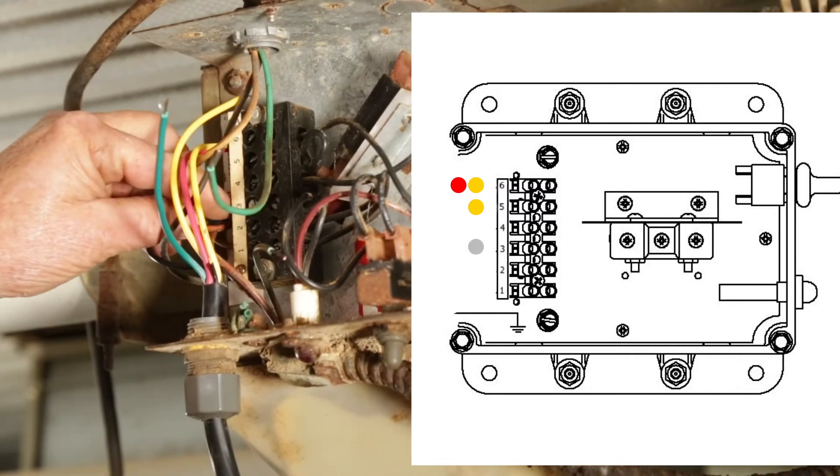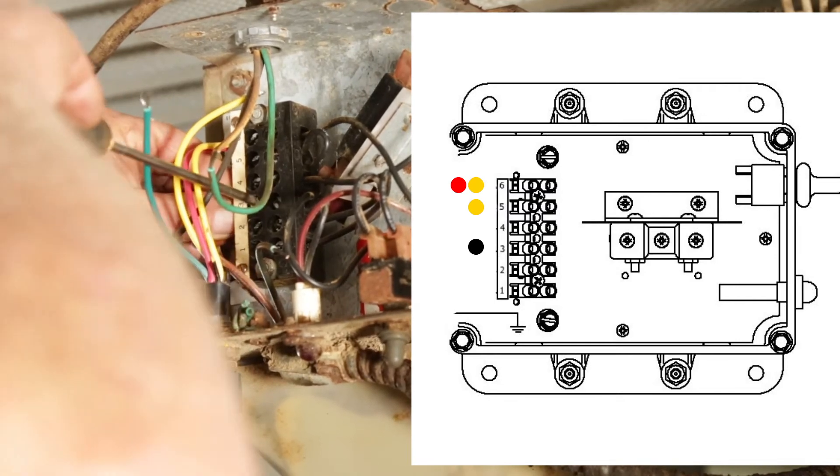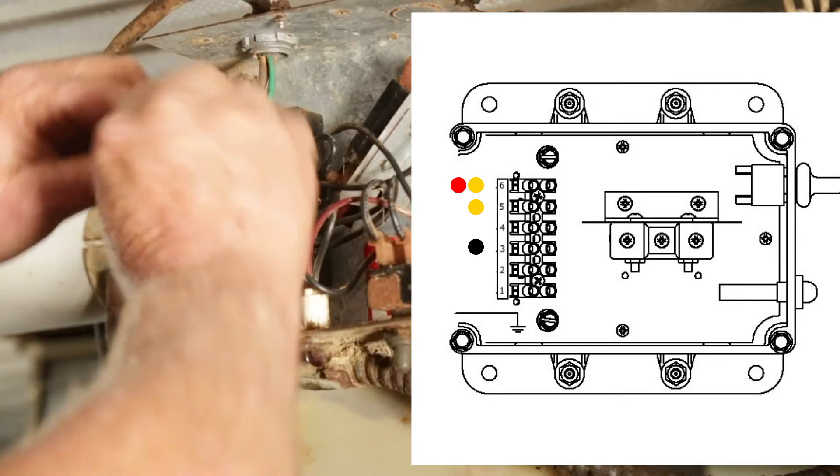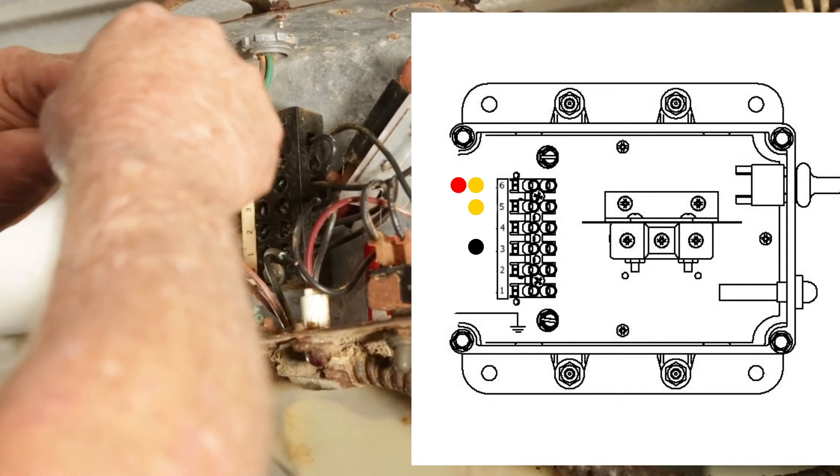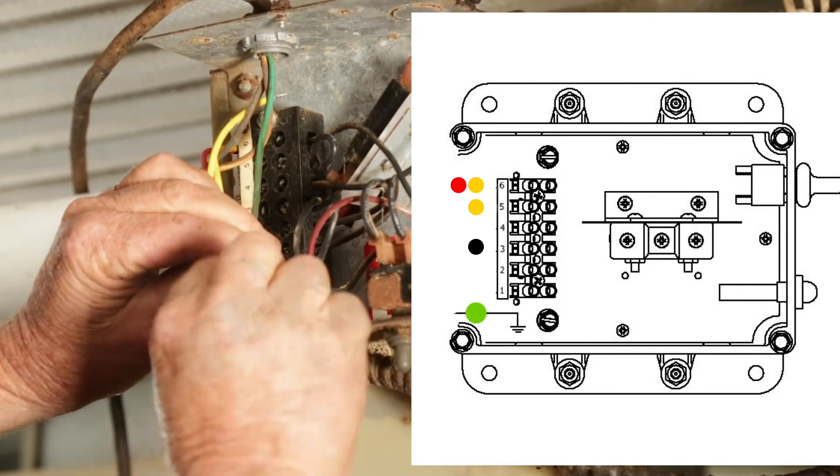Connect a black wire from the HS820 to the number 3 slot on the chore time terminal. Last, conjoin the green wire from the HS820 to the green ground wire of the chore time control box and cap them with a wire connector.